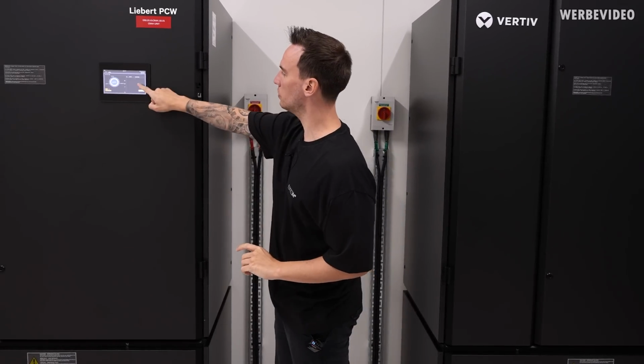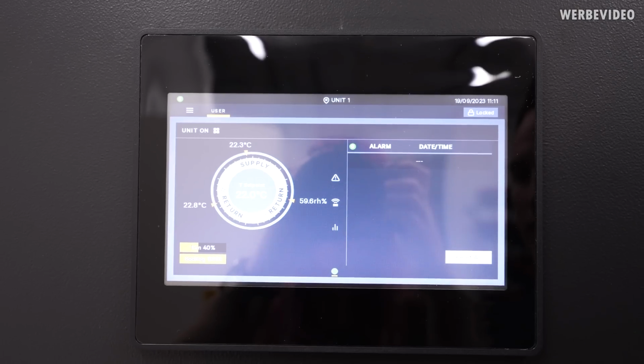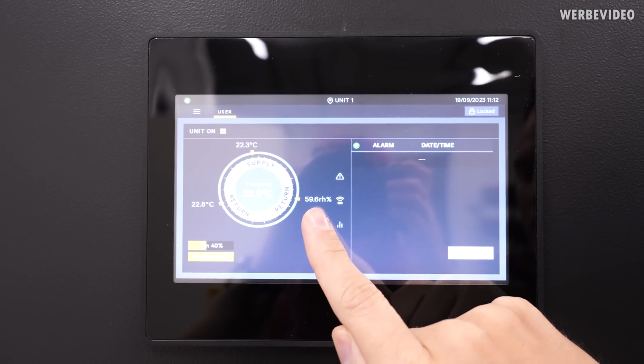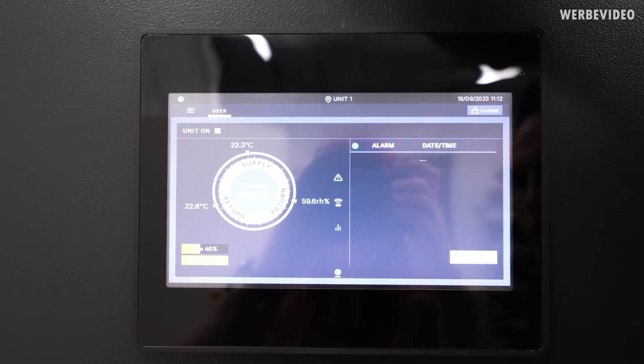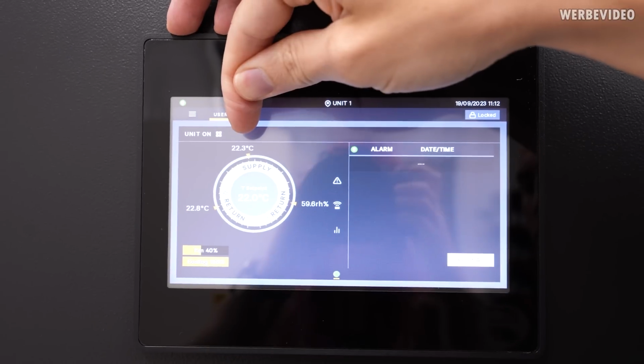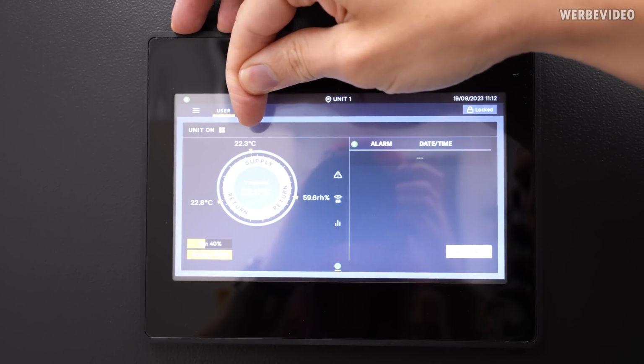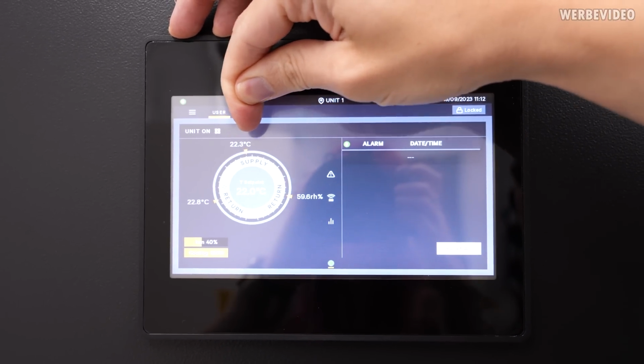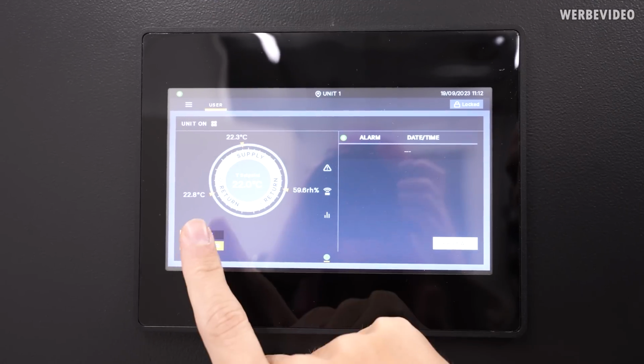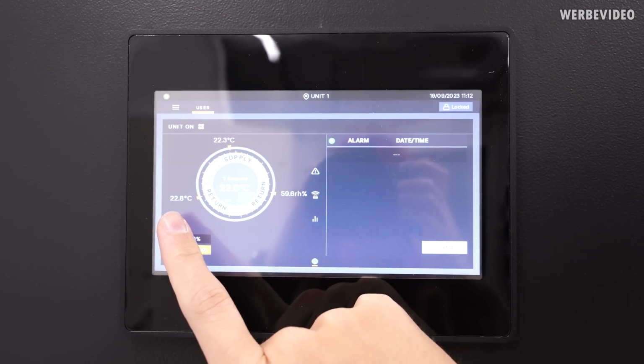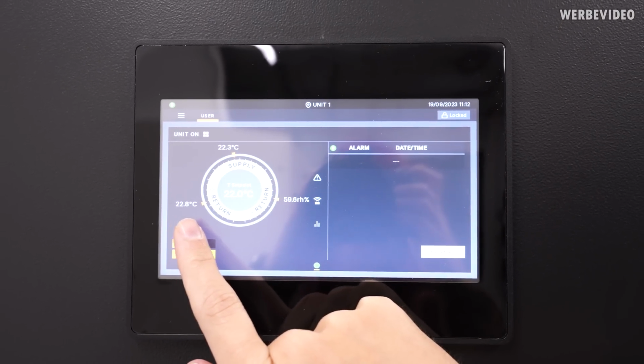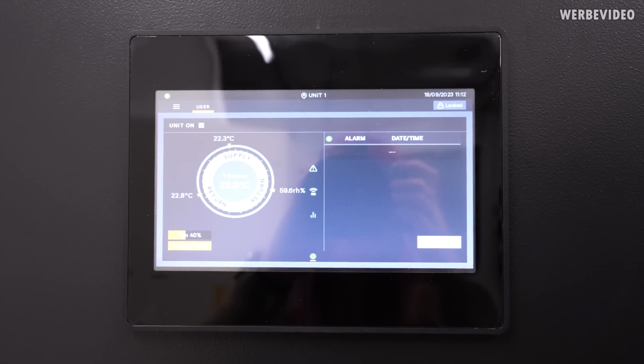We can also take a look at this right here. We can see that we run at about 60% humidity inside, and the cold air supplied from the cold water is at 22.3 degrees Celsius, while the returned warm air after exiting the UPS and the rest of the room comes back at about 22.8 degrees Celsius.